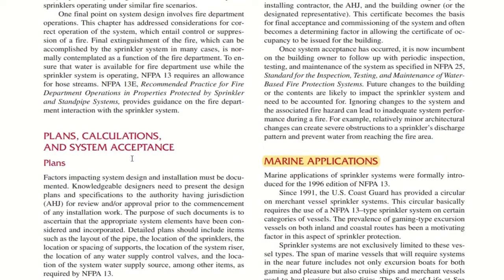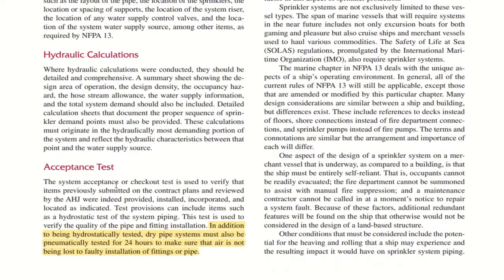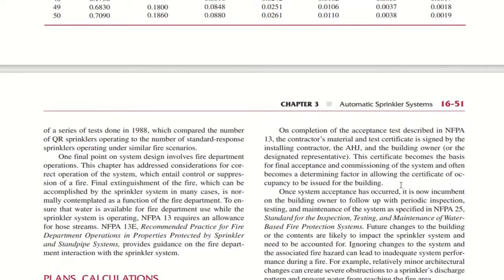So plans, calculations and system acceptance tests. In addition to being hydraulically or hydrostatically tested, dry pipe systems must also be pneumatically tested for 24 hours to make sure that air is not being lost to faulty installations of fittings of pipe. This is an important point.